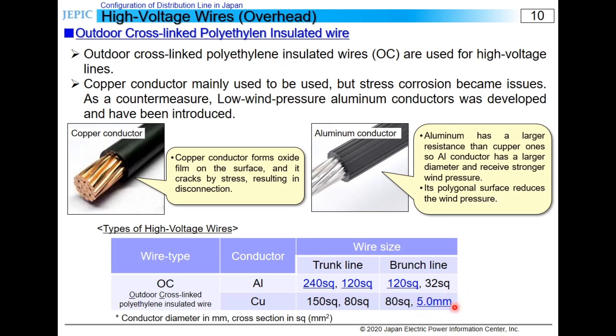Allowable current of 240 square is 512 amperes, equal to about 5,600 kilowatts. That of 120 square is 308 amperes, equal to about 3,400 kilowatts, and of 5 millimeters is 142 amperes, about 1,500 kilowatts. 5 mm wires are used in branch lines with small load, but when it's near a substation, 120 square wires are used so that disconnections don't happen due to a large short circuit current.